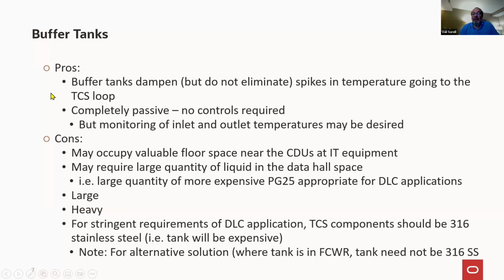You can still monitor temperatures, and that actually introduces a really interesting point of view. If you do monitor the temperatures into the tank and out of the tank, under normal situations the temperature would be the same. When you have a sharp spike, the inlet temperature will be very much higher than the outlet temperature. That can become an alarm that sends a signal to the chiller plant saying, it's coming, be aware. It's like a feed-forward loop to say, you have a minute to start, because we don't know what the residence time of the facility hot water is before it hits the chiller. But if we have that 1 minute or so, or maybe even a 2-minute advance notice, that may actually enable us to reduce the size of the buffer tank. That is all something that needs to be included in the sizing of the tank.